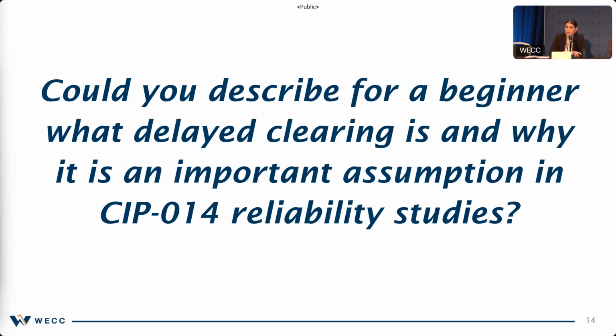The safe assumption is that local protection system is not available, or is not able to respond appropriately. The delayed clearing is downstream looking toward your system. So if you have fault detection at your facility, you're not just looking internally, you're looking down each transmission line to determine if there's faults further away. There will be an intentional delay that disconnects and isolates that fault if you detect it and it's not isolating at the other end. That is the intention of delayed clearing. It's a redundancy with a built-in time delay, and it's intentional. That's what's expected in the CIP 14 studies—the assumption that your local protection system will not be available, and you'll have to rely on delayed clearing from outside protection systems looking in.